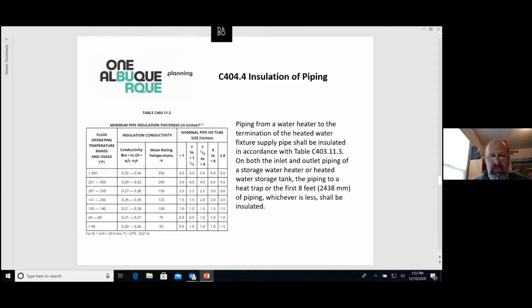Dave, this is Lance. Sorry. Just as a general approach to the energy code, if you're not changing anything, the new code doesn't apply. So if you don't have to change the piping and you're just changing out the equipment, then you won't have to adjust the piping unless, of course, the equipment requires it. But that applies to everything in the energy code. It's truly this, you touch it, you buy it idea. If you just leave it alone and it's obviously safe and code compliant, then the new requirements of the energy code would not necessarily kick in.